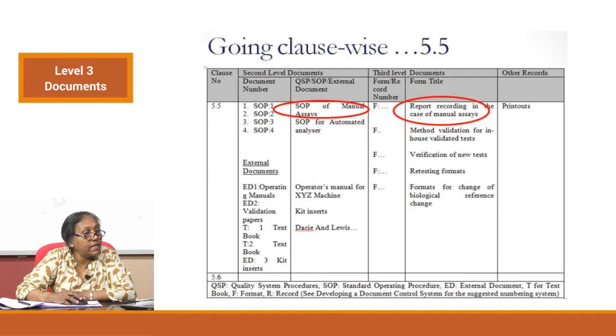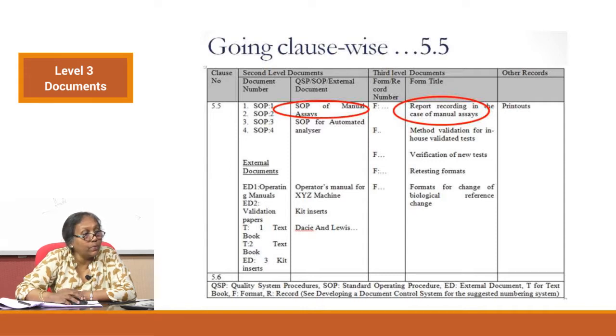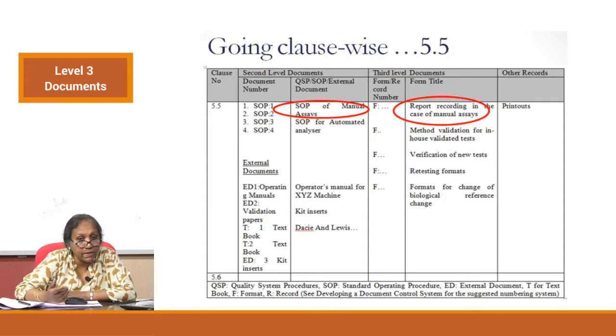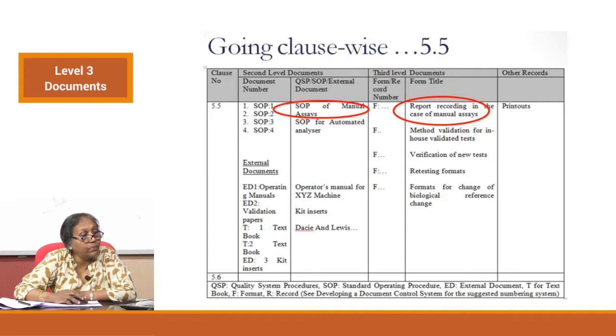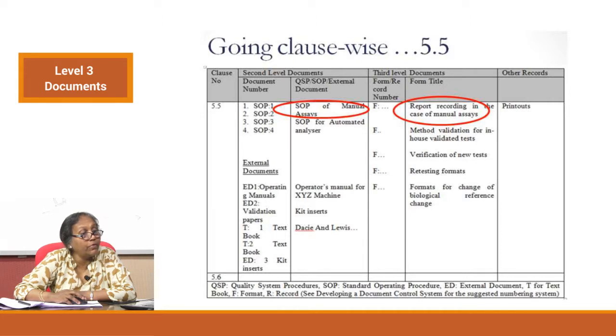This is how you think through the scope of proof required for an activity. For any format you make, think it through and decide what proof is required and put that in the format. Let us look at another example in the technical requirements: clause 5.5, examination procedures. In the reference table under the quality manual for 5.5, this laboratory has four SOPs. The first SOP is for manual assays — manual assays definitely require formatting for a lot of things, such as report recording of manual assays.